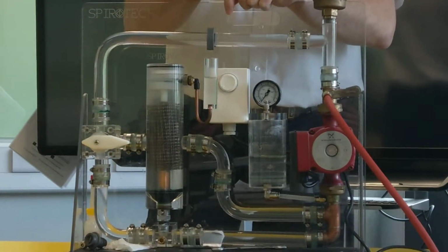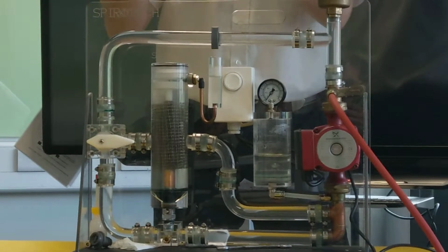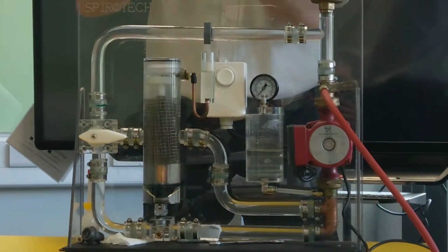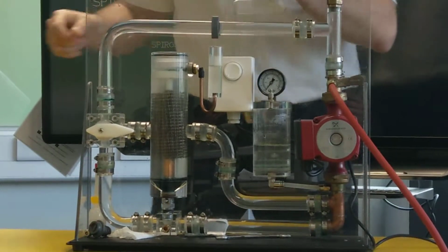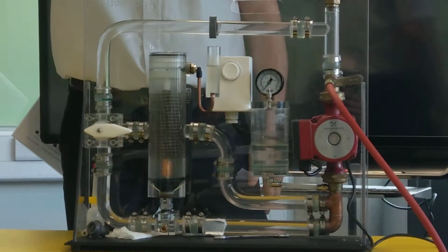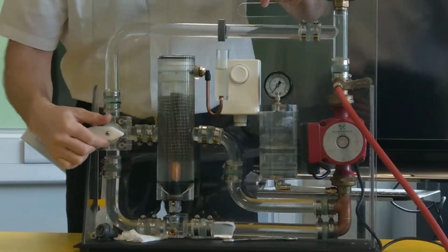So we need to expel these gases. As the heat exchanger is heating up this water from 30 to 80 degrees, and these are being formed in the heat exchanger on the walls, before the flow carries them into the system, we need to expel these. And that's the job of this item, the deaerator. Okay. So let's see what she does.